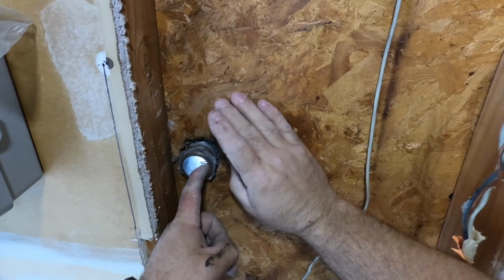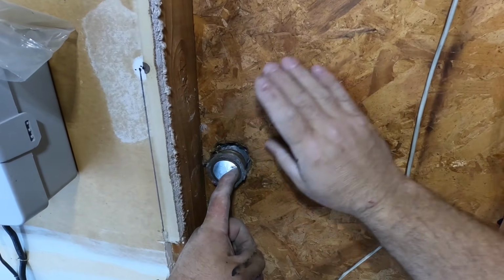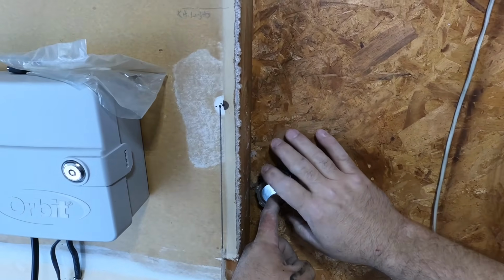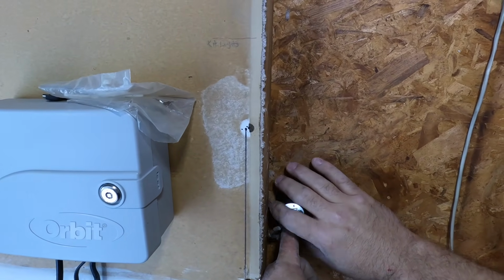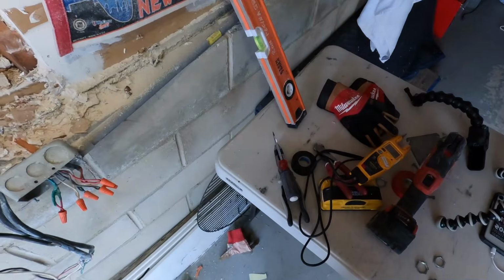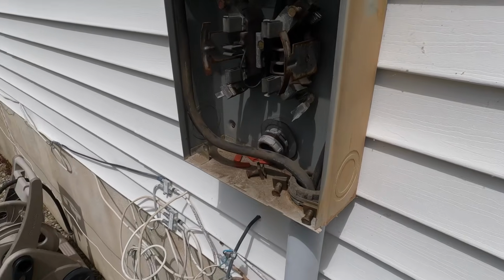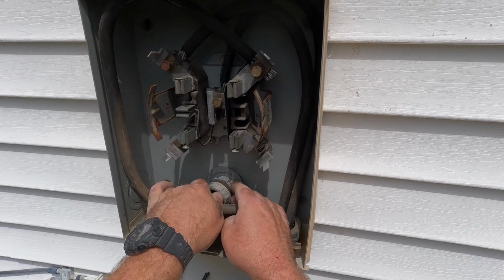The 2-inch nipple is needed to run the big 2-aught copper conductors that are going to go through it. I think I could get away with 1.5 inches, but I'm so used to using 2-inch, and it just makes life easier. So if I can get a 2-inch chase nipple in there, I'm going to do that, or a close nipple, I should say.